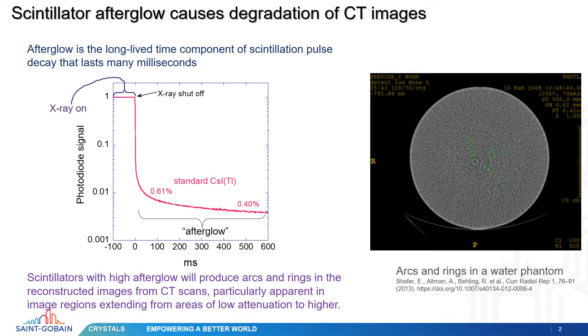Scintillator afterglow is a bad thing and it causes degradation in CT images. To define it, afterglow is the long-lived time component of the scintillation pulse decay that can last for many milliseconds. The plot here shows the scintillator photodiode signal versus time in milliseconds. The time from minus 100 to 0 milliseconds shows the diode signal when the x-ray beam is on. We normalize that to 1, and then when the x-ray beam is shut off at time 0, the scintillator continues to emit scintillation light, still putting out light at a rate of 0.61% of when the x-ray beam was on.